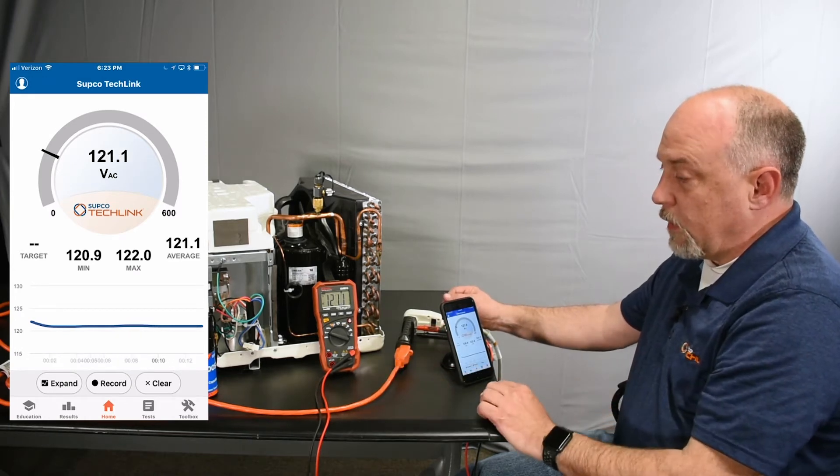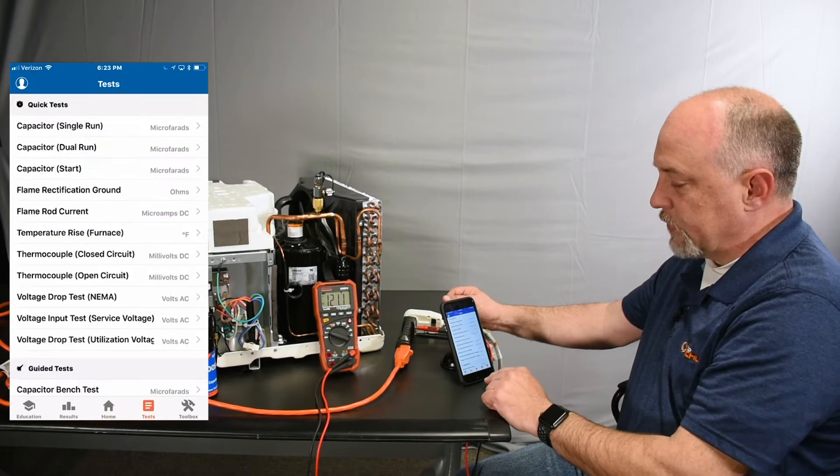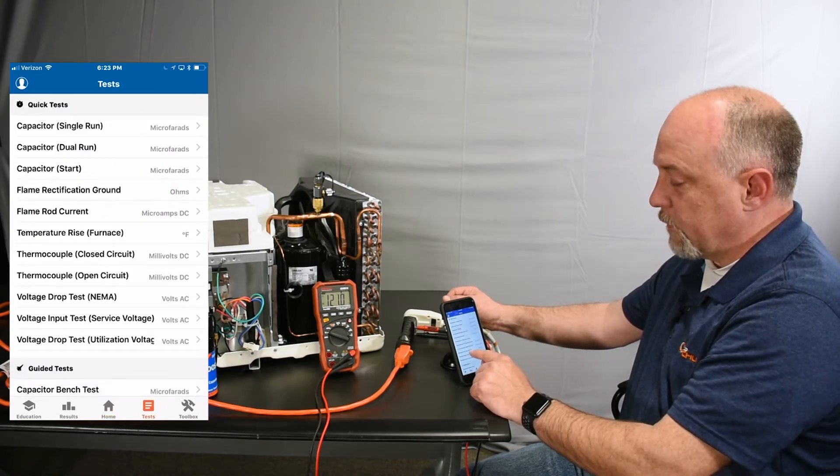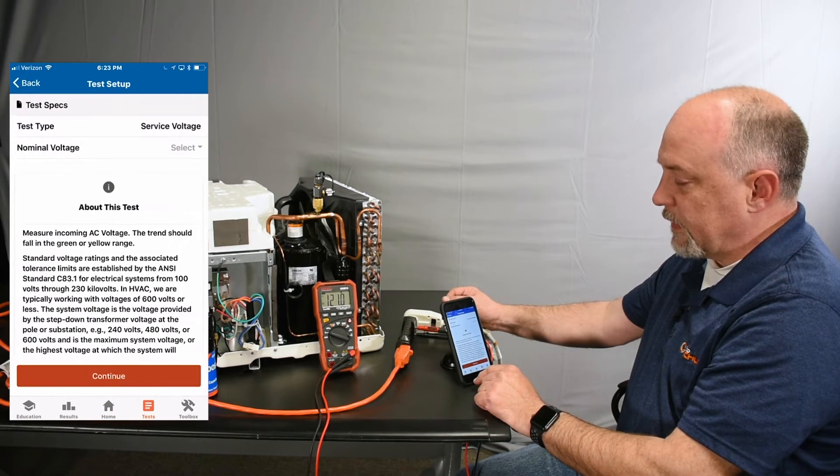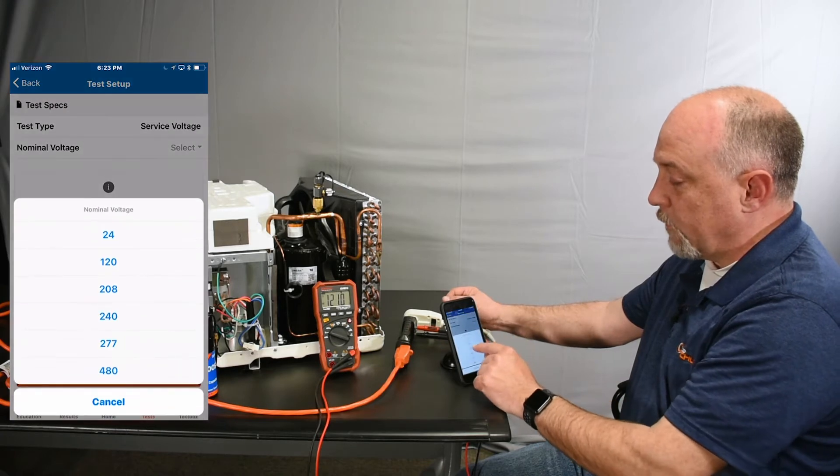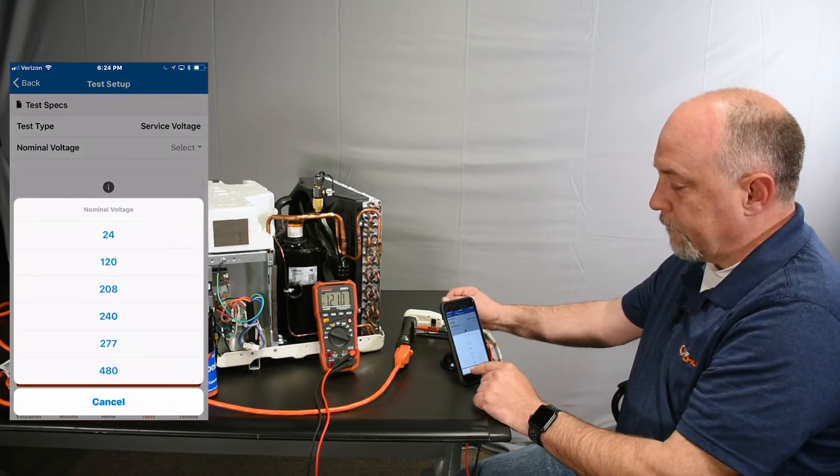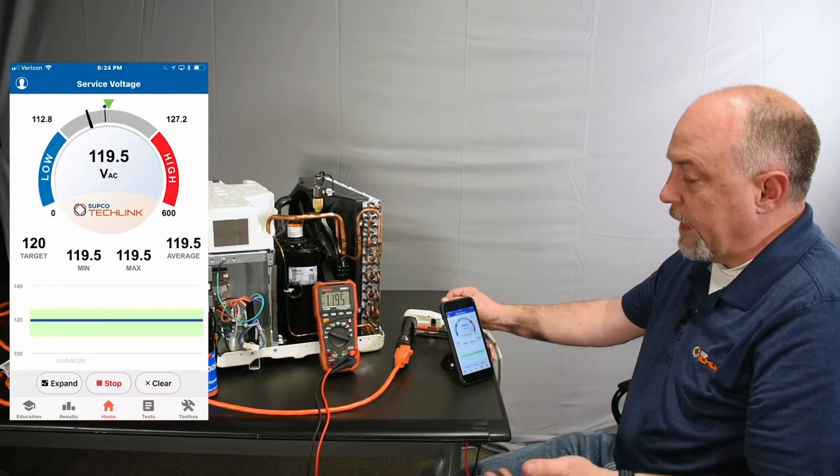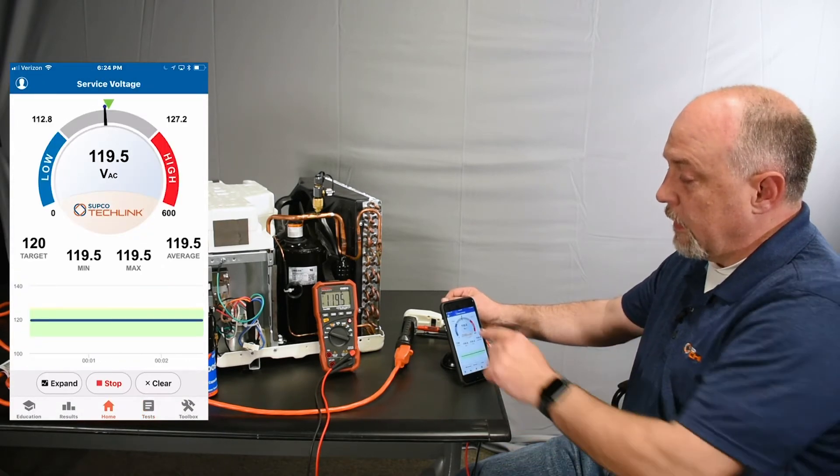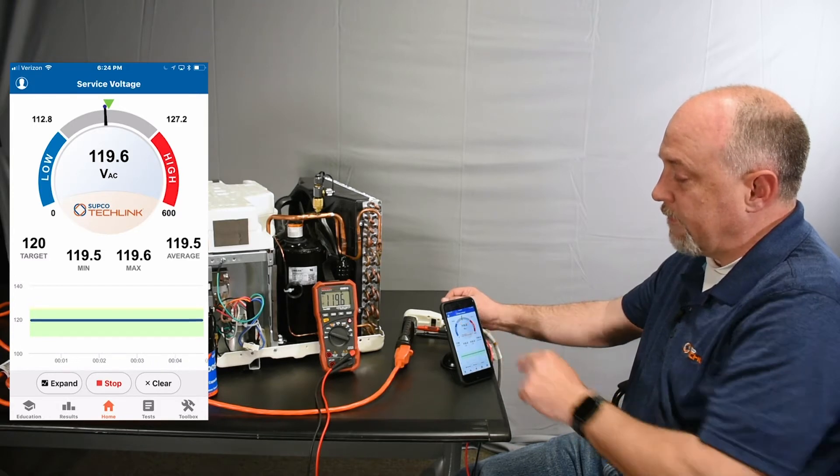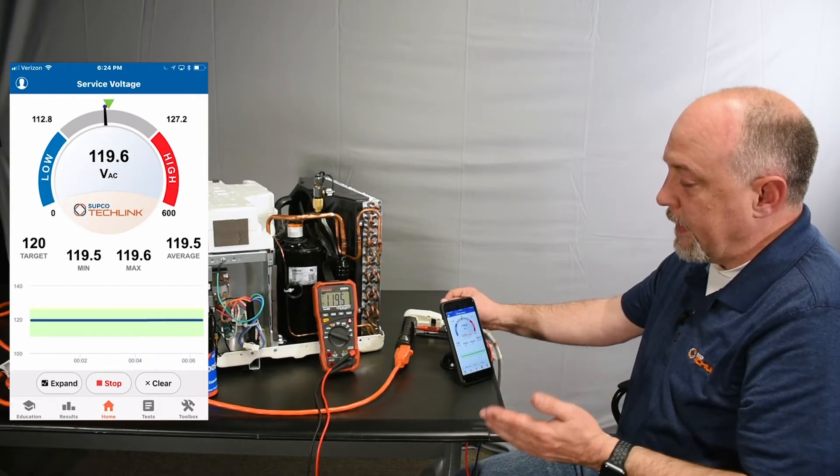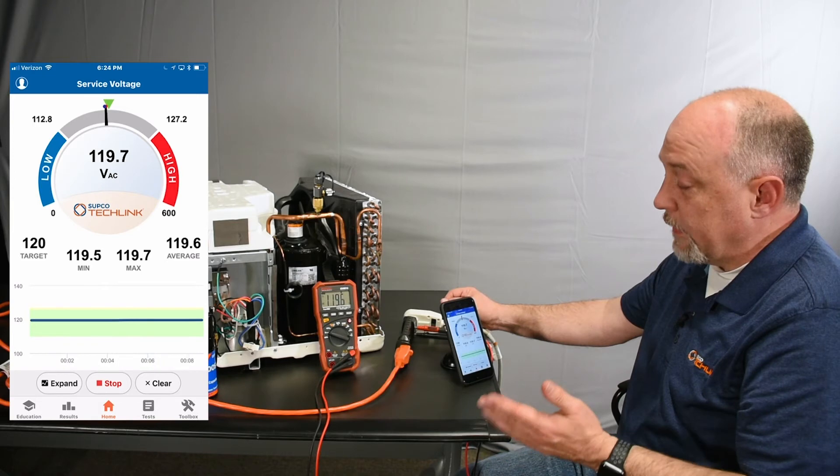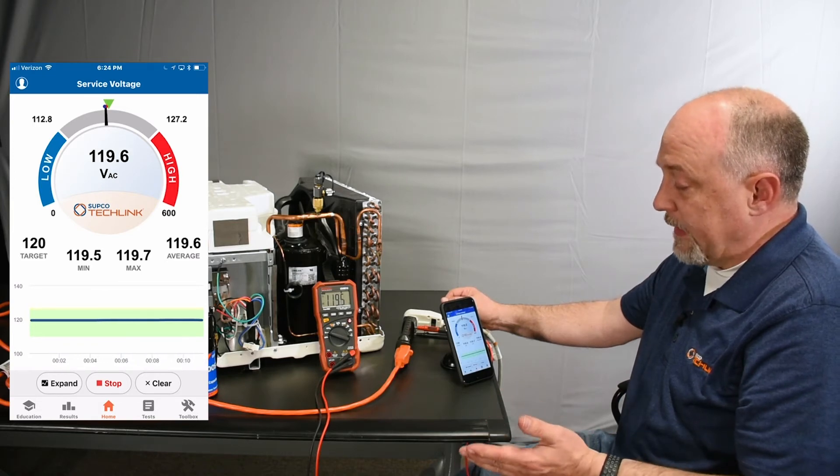Right away you can see I have 121 volts and I'm going to start a service voltage test. We select service voltage, select nominal voltage which is 120, and hit continue. It tells us the high and low range: 112.8 to 127.2. We're right at 119.5, so we're right in the center where we should be and everything looks great.